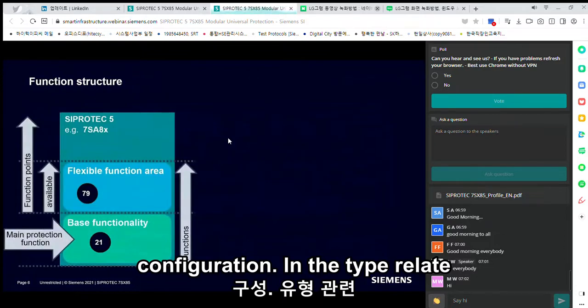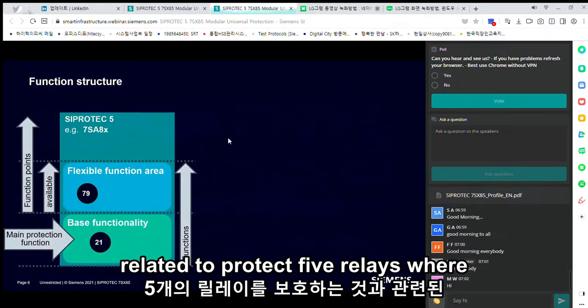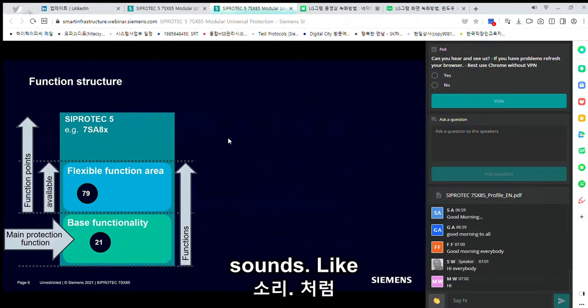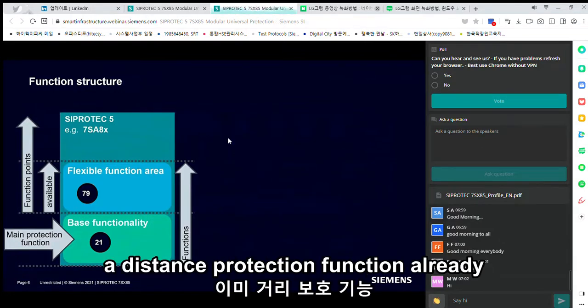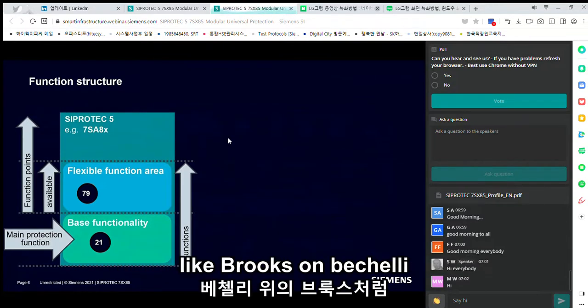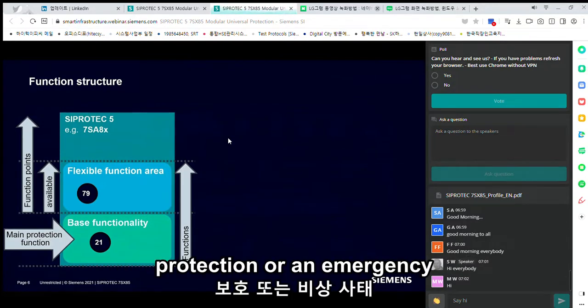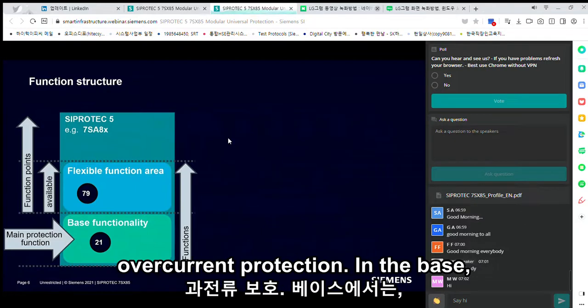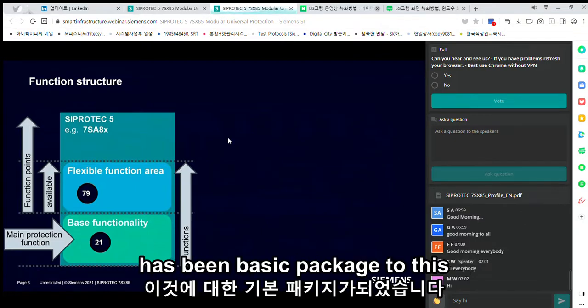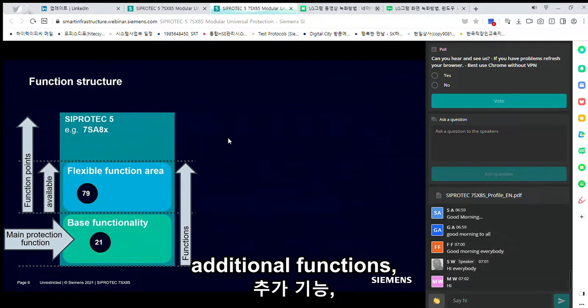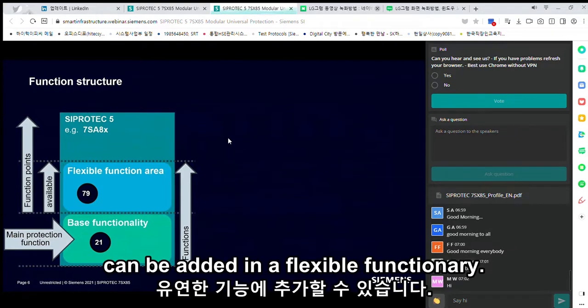In the type-related SIPROTEC 5 relays, we have so-called main protection functions, like a distance protection function, already together with additional functions like teleprotection or emergency overcurrent protection in the basic package. To this, additional functions like auto-reclosure can be added in a flexible function area.